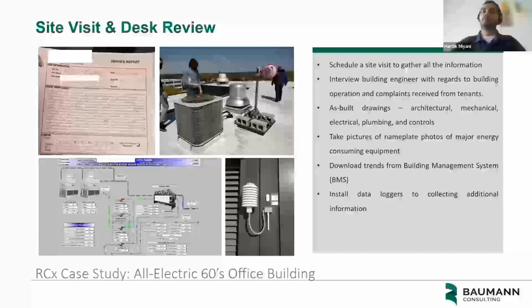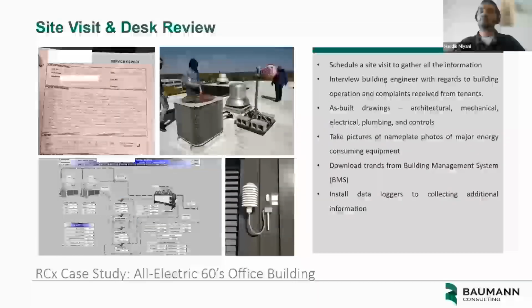As you can see in the image at the right bottom, that was a Hobo data logger that we installed on this facility. The Hobo data logger logs data like the ambient temperature and humidity. Later on, we compare it with the sensor reading that is provided in the building. This helped us verify how much the deviation was from the actual reading. We installed this data logger for a period of 2 weeks in order to get different samples, and it was set for a 15 minute time interval.